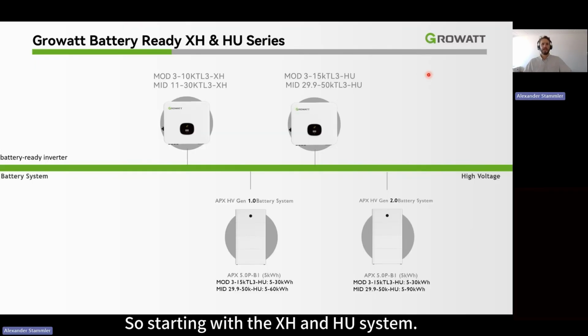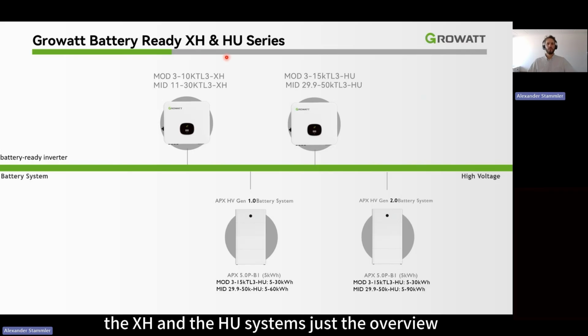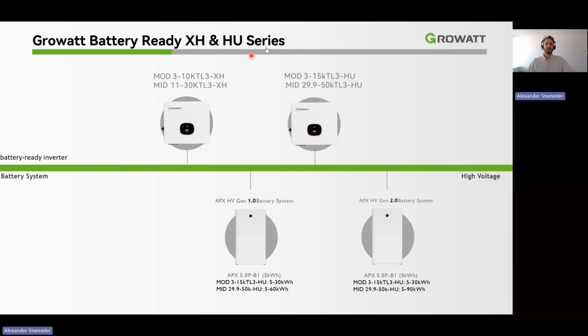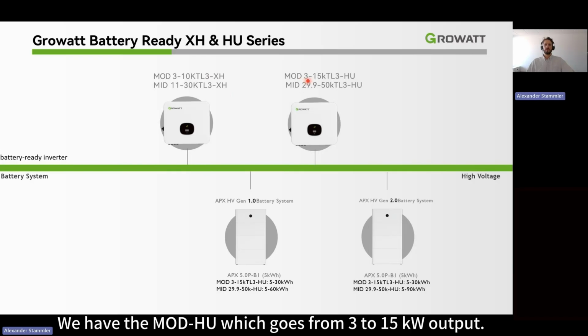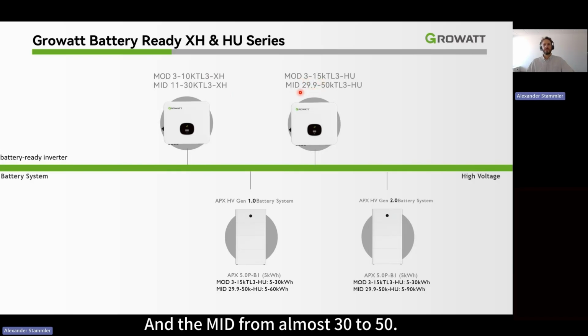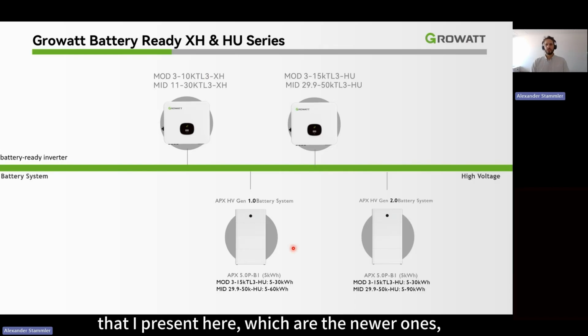So, starting with the XH and HU system. These are the battery-ready systems for us, the XH and the HU systems, just the overview. We have the MOD from 3 to 10 kilowatt AC output, and the MID is from 11 to 30 kilowatt AC output. We have the MOD HU, which goes from 3 to 15 kilowatt output, and the MID from almost 30 to 50. Then we have two different battery systems that I present here, which are the newer ones. The APX system, which we can do with the MOD, we can do up to 30 kilowatt hours of capacity. The MID can go up to 60 kilowatt hours of capacity.